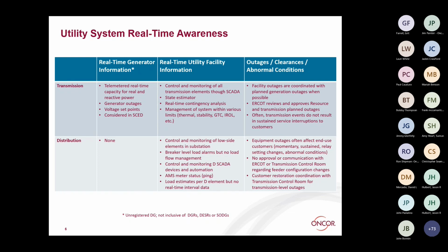In distribution, where you have radial lines, it is a very different situation. So when you have abnormal conditions or you take something out for construction, you would actually cause an outage. That is not a networked setup, and it's not very stable, if you will. So what we have to do is isolate that area, limit that clearance to where it doesn't affect customers, and then reroute that power by closing a switch from a neighboring facility to bring that in.